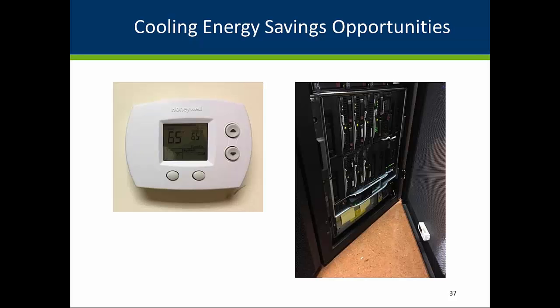Now let's consider cooling savings opportunities. ASHRAE recommends that server rack inlet temperatures are maintained in the range of 64.4 degrees Fahrenheit to 80.6 degrees Fahrenheit. Consequently, thermostats could be adjusted to set points that deliver air temperatures as high as 80.6 degrees Fahrenheit at the front of the server racks.